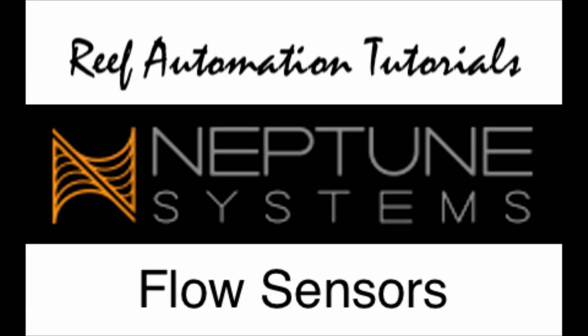If you have an ATK system, what's nice about the ATK system is it comes with 2 additional ports that you can use for any type of FMM accessories, including flow sensors. So they make a 1/4 inch, a 1/2 inch, a 1 inch, and a 2-inch flow sensor. So if you're trying to do something maybe at 3/4 inch, for instance, which is a common size, or 1 1/4 or 1 1/2, I always recommend that you do the larger flow sensor, and therefore you put the smaller pipe into the larger flow sensor. That seems to get the more accurate flow.